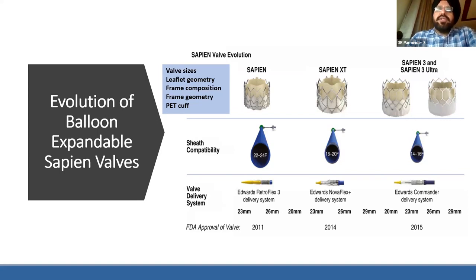The frame composition has changed. Earlier the frame was stainless steel, now it has been changed over to cobalt chromium alloy, which has thinner struts but still maintains strength. The frame geometry has also improved, with the upper cells becoming larger for better coronary access in case it is deployed relatively higher. And there is a cuff around the lower cells for preventing aortic regurgitation, which is also a recent addition. Further, the sheath compatibility has decreased from 24 French to 14 French, and delivery systems have improved a lot over a period of time. So this is the evolution that we observed in the SAPIEN 3 valve.